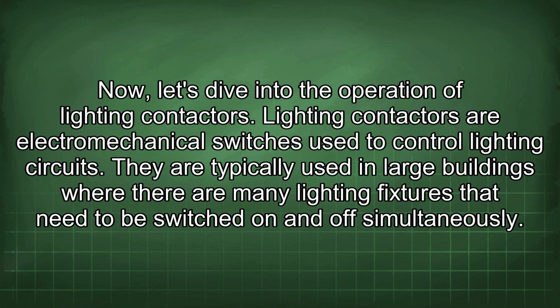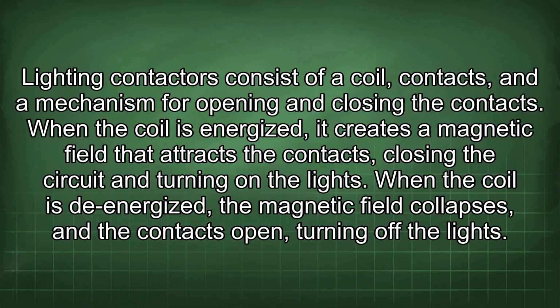They are typically used in large buildings where there are many lighting fixtures that need to be switched on and off simultaneously. Lighting contactors consist of a coil, contacts, and a mechanism for opening and closing the contacts. When the coil is energized, it creates a magnetic field that attracts the contacts, closing the circuit and turning on the lights. When the coil is de-energized, the magnetic field collapses, and the contacts open, turning off the lights.